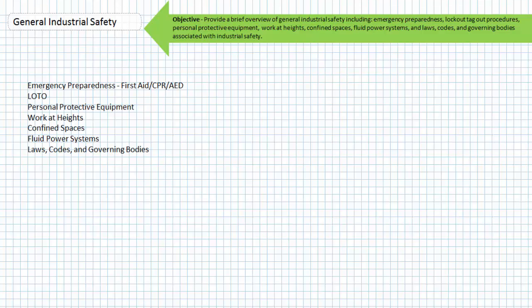The general procedure used to prepare a system for service follows this scheme. Step 1: Have a plan. Know where all the lockout points are on a particular system and have the means of locking them out available. Step 2: Notify all affected personnel and shut down the system.